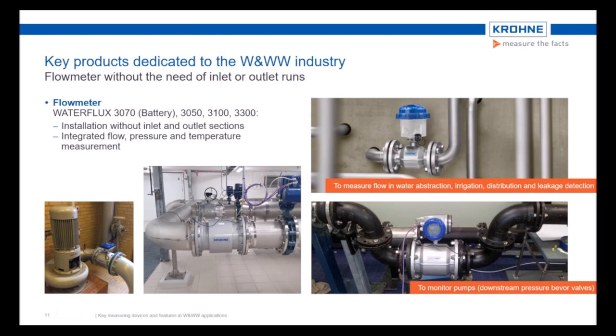First of all, we would start with a special flow meter, which is dedicated for the water industry to measure flow in water abstraction, irrigation, distribution or leakage detection. This flow meter can be connected to several converter units to provide different features such as signal communication or also different power supply options. The Waterflux 3070, for example, is a complete standalone, energy-autarkic water meter which will be battery operated. So independent of the connected converter, this flow meter can be installed without the need of any straight inlet or outlet sections, in fact covering the whole diameter range from diameter 25, so 1 inch, to diameter 600, which is 24 inch. Thus, installations demonstrated on the picture are possible.